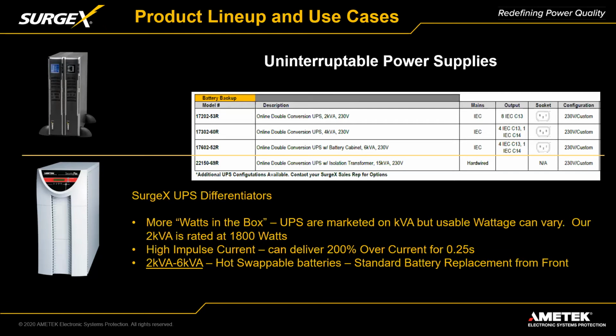The other big differentiator is high impulse current delivery - 200% overcurrent for a quarter of a second. What that means is AV equipment, when you turn it on, is not going to trip the UPS to turn off, because when you're a double conversion online UPS, you are now the source of the power.